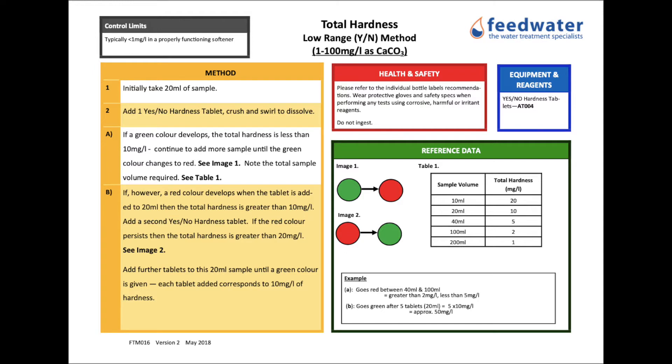The range for this method is 1 to 100 mg per litre as calcium carbonate and for a properly functioning softener results are typically less than 1 mg per litre.